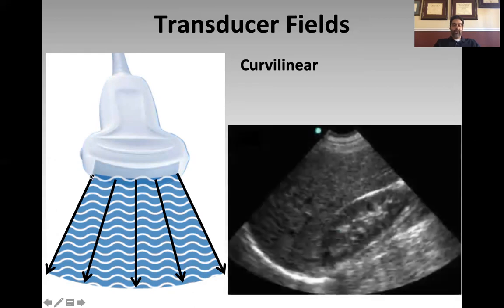The curvilinear probe has its crystals arranged in a curvilinear fashion, parallel to the nose of that probe. When those crystals vibrate, they send out sound in a sort of windshield-wiper path-shaped field, which produces an image shaped like that. Again, the dot on the probe correlates with the dot on the screen.